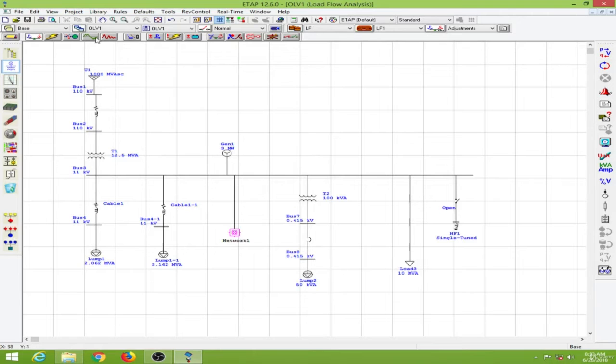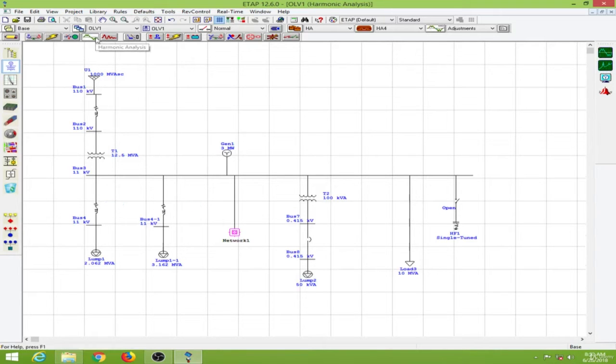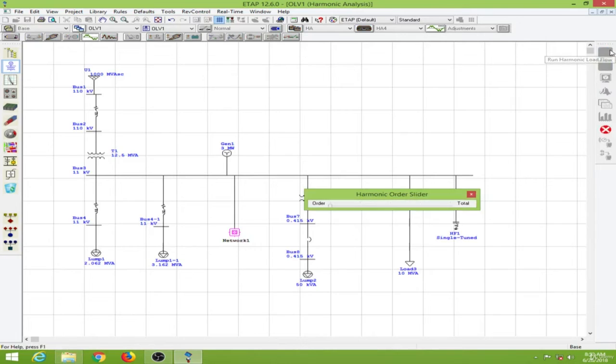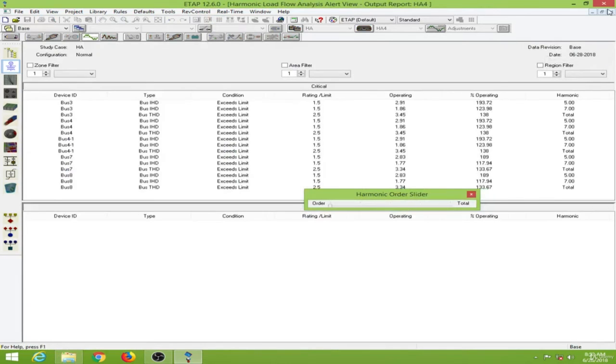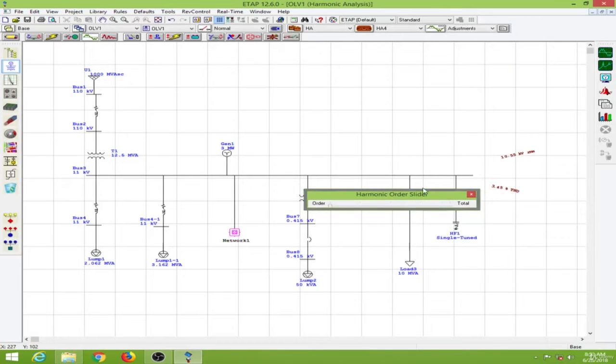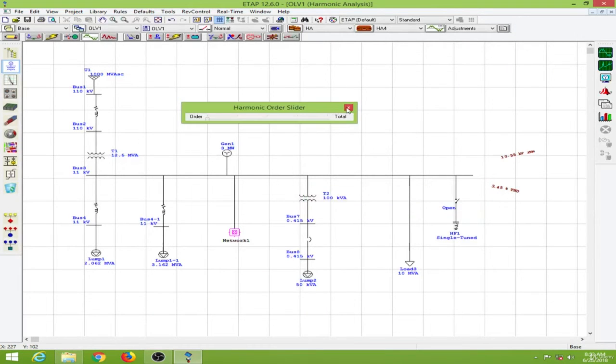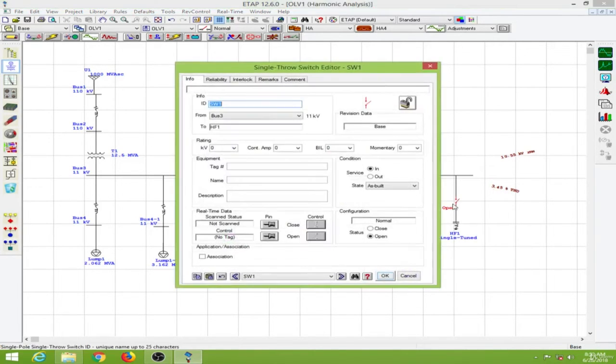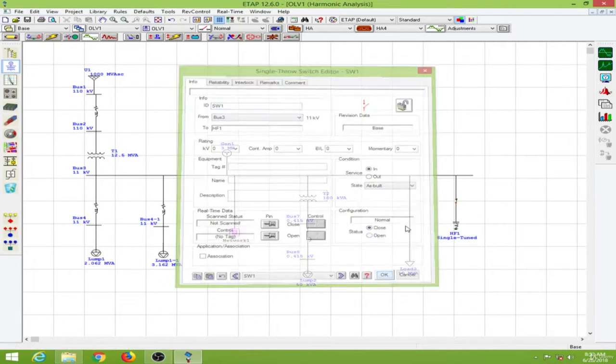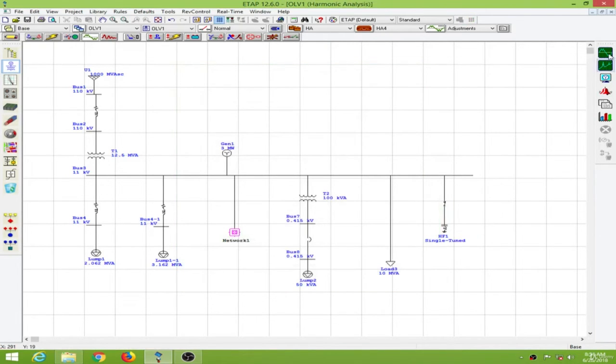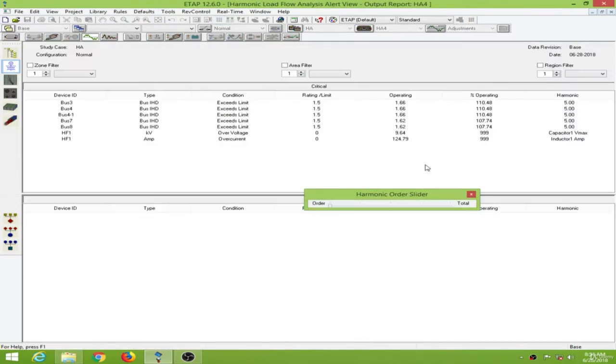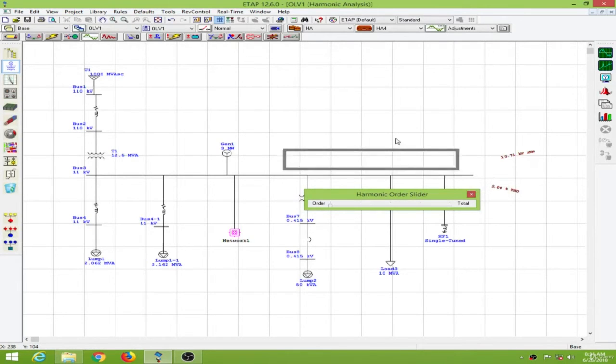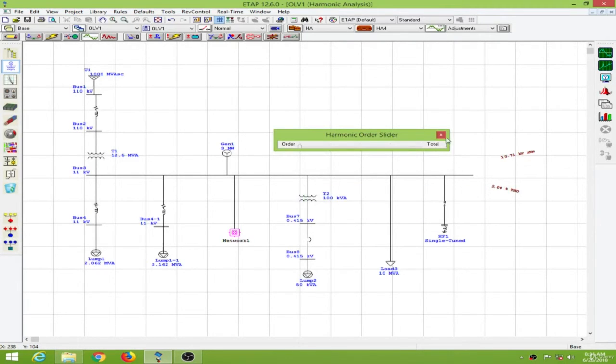Going to the harmonic analysis, let me conduct a harmonic load flow. Now the total harmonic distortion is about 3.45%. Let me close the harmonic filter and conduct the harmonic study. Now the THD value has reduced to 2.04%.